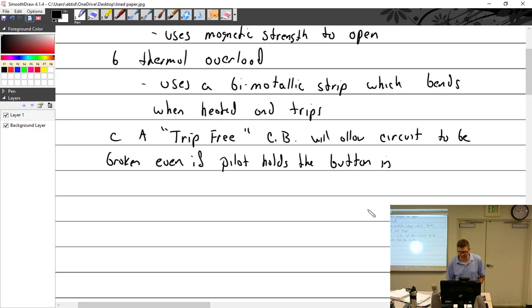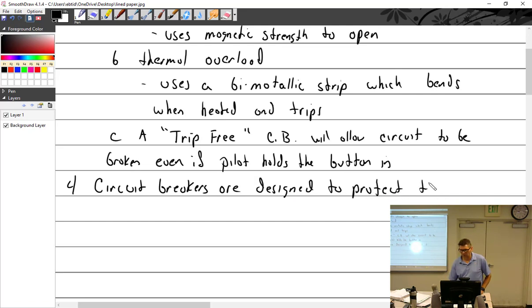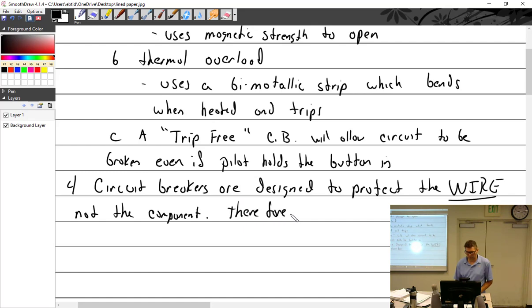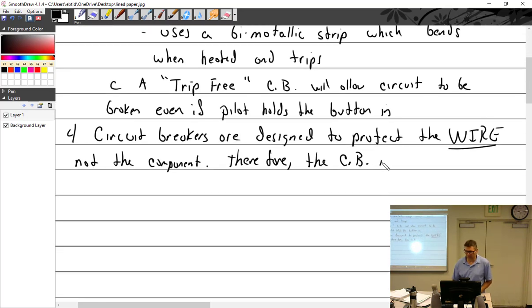All right, big point here: circuit breakers are designed to protect the wire—you got to remember that, write it down, remember it. Circuit breaker protects the wire, not the component. Therefore, the circuit breaker must trip below the capacity of the wire.